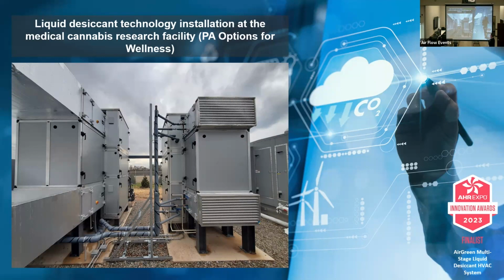This is what we have: 2 units outside at this grow facility. We have 2 3,000 CFM conditioners, and we have 2 2,000 CFM regenerators. The regenerators are more efficient to run, so they don't need to be as big. Our package units, which I'll show, actually have a built-in side-by-side conditioner and regenerator all in the same box, fans, coils, all that. This was, again, 2 years ago.